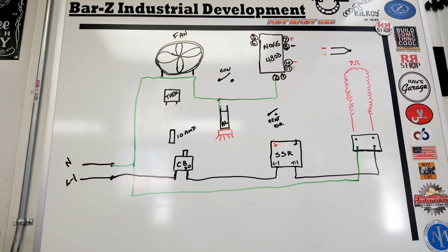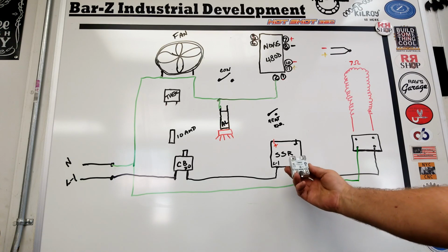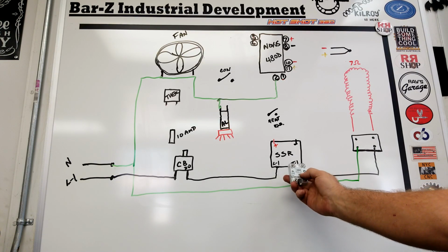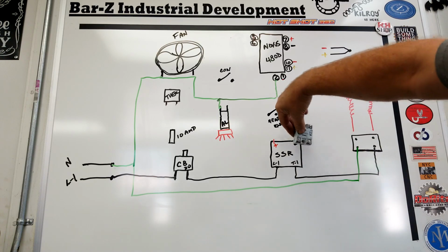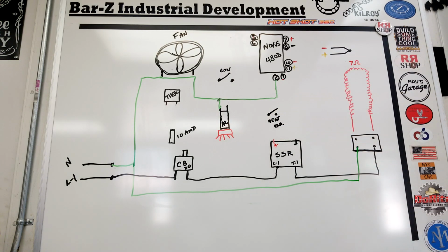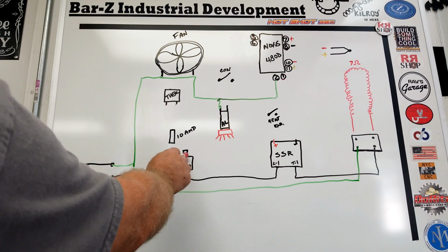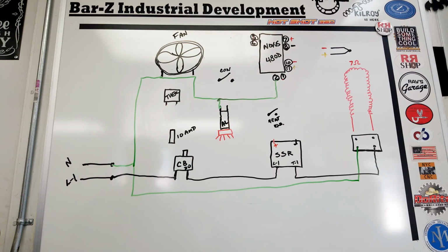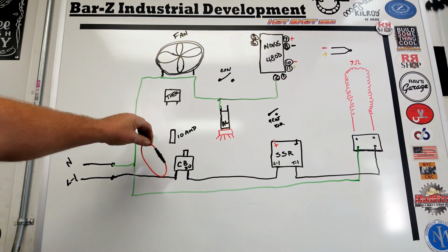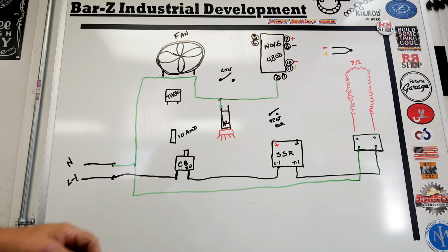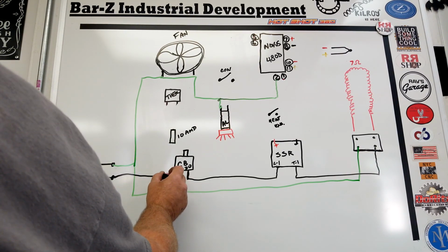From there, if you want a representation, there's the SSR right there with the L1 and the T1 connections. They're actually upside down like that. Okay. All right. Next up, we're going to come out in this connector where you make this first initial connection into this main circuit breaker, the 20 amp circuit breaker. You're going to go ahead and drop in this little fuse right here and branch out of that. So you're going to make a connection within that terminal, come out and hit that 10 amp breaker.